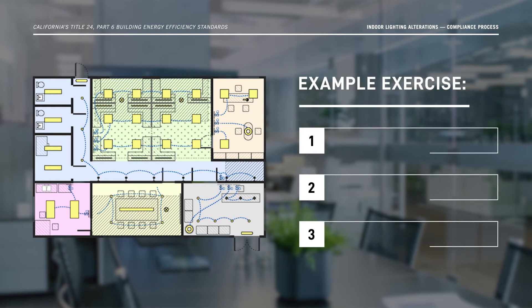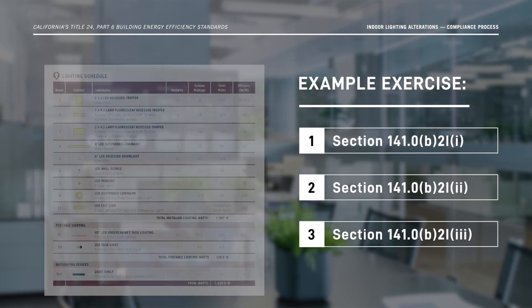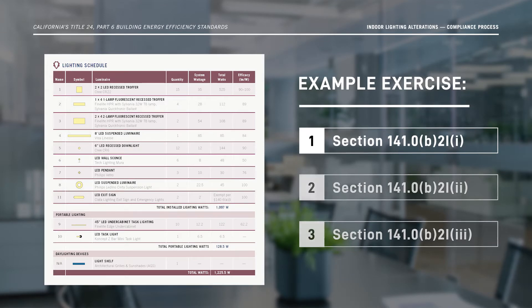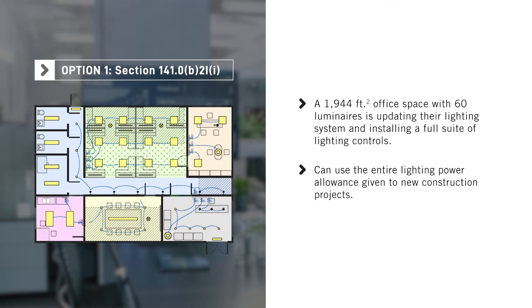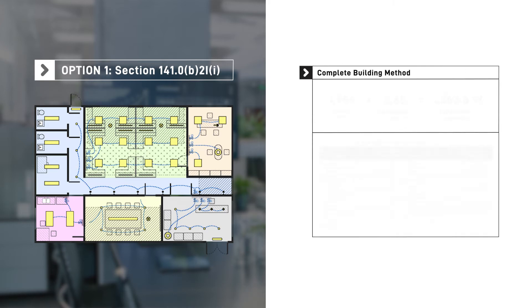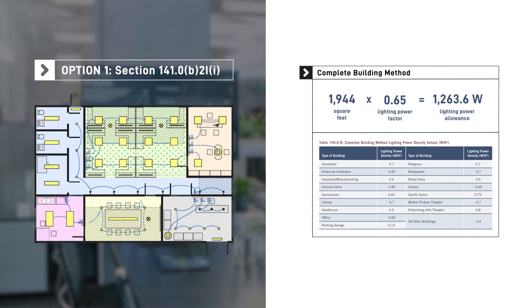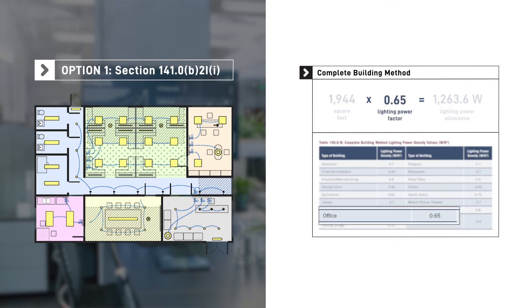Now let's walk through a sample project using each compliance pathway, starting with Option 1. A 1,944 square foot office space with 60 luminaires is updating their lighting system and plans to install a full suite of lighting controls to meet their green building goals. This means they can use the entire lighting power allowance given to new construction projects. For simplicity, the design team decides to use the complete building method to calculate the lighting power allowance. This calculation requires multiplying the square footage of the building by the allowed lighting power factor for that building type found in Table 140.6-B.